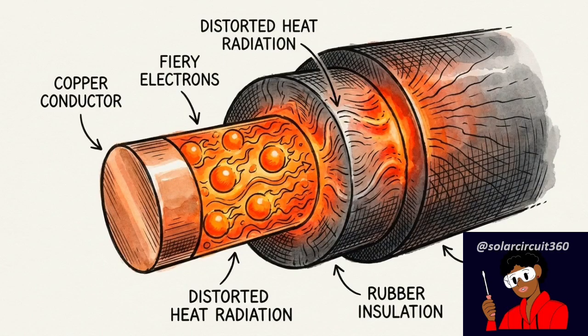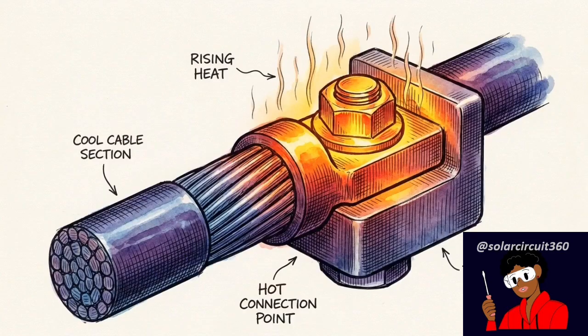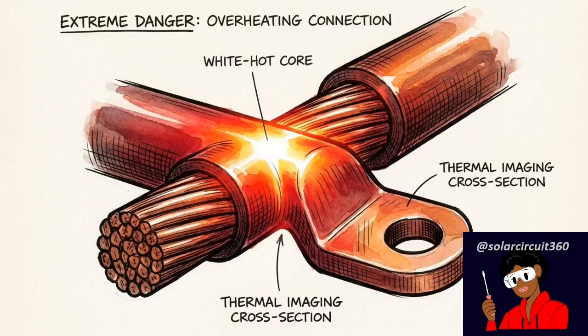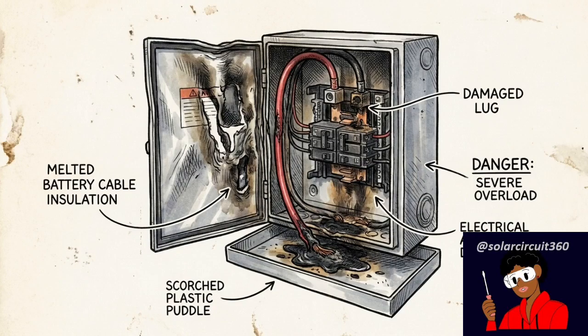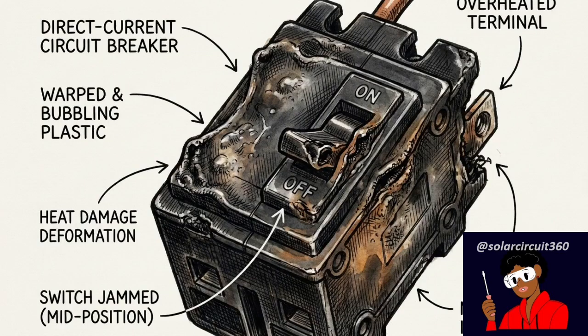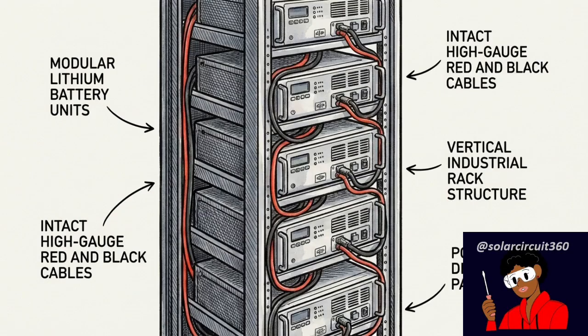raw heat. This thermal imaging cross-section captures what happens to a slightly undersized copper cable under that exact load. The bright red zones show dangerous thermal buildup, localized at the terminals. Sustained exposure to this heat melts insulation, scorches busbars, and causes low-quality direct current breakers to mechanically warp and fail under pressure. Even if the physical wiring survives the heat, the massive current draw creates a secondary issue.